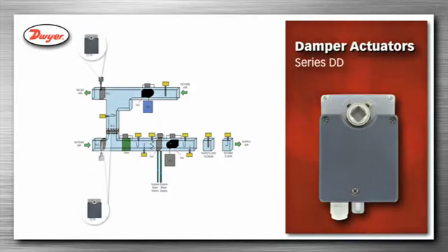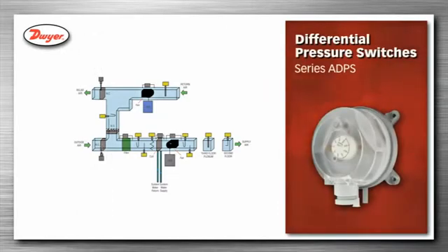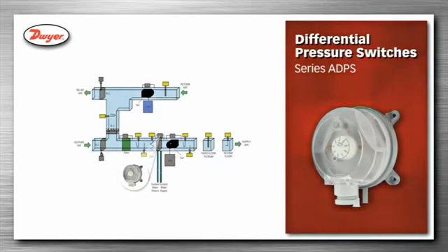Damper actuators, series DD, are used to open and close dampers to change the airflow through the air handler. Differential pressure switches, series ADPS, are used as a frozen coil alarm by monitoring the pressure loss across the coils in the duct to indicate a frozen coil condition. They are also used as a dirty filter alarm by monitoring the differential pressure loss across the filter.